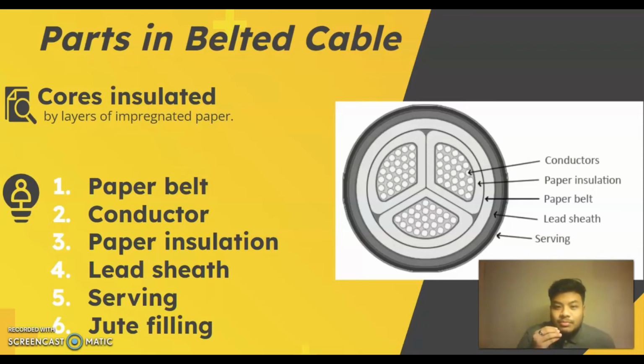So a second layer of impregnated paper tape is known as a paper belt, which is number 1, and is wrapped around the grouped insulated cores. And in order to give the cable a circular cross section, the gap between the insulated cores is filled with fibrous insulating material, which is jute filling. And the cores are usually shaped and may have a non-circular form to maximize the amount of area available.